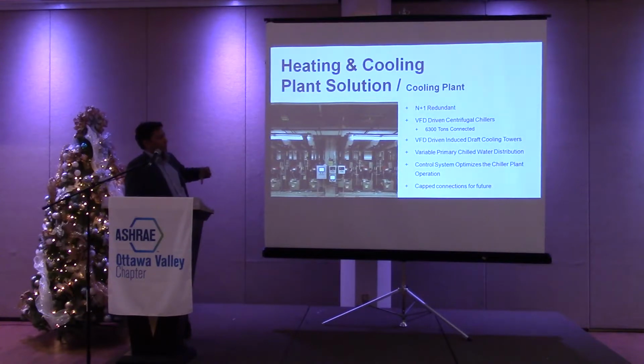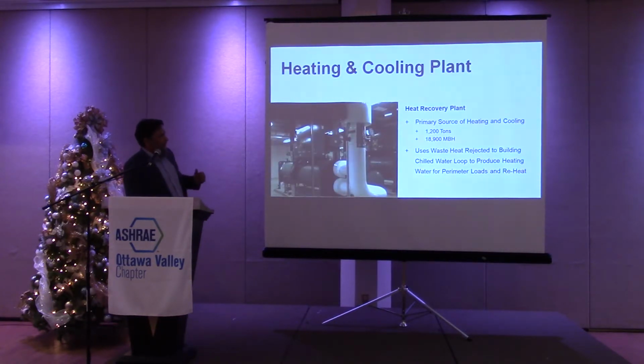it takes a lot of tweaking, because energy optimization sequences aren't focused on heat recovery systems, and they have a hard time recognizing that heat recovery chillers, even though they've got high kW per ton, aren't as efficient in cooling, but you gain the benefit of the heating side, so you've got to take that into account. And it's amazing that one little simple thing can throw your standard control optimization sequences out the window. And so we have to work with the controls vendors to ensure that they help on that. So again, I touched on this before.